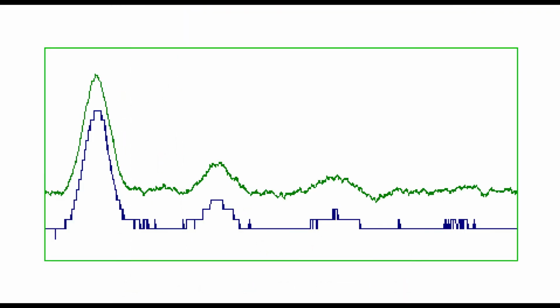The following figure shows the same chromatogram as before with a small amount of noise added. The noise appears as quantum hairiness on both the baseline and the peaks. When the noise spans several steps, the hairiness fades, and the quantized noise appears as shown in the first figure in this section. Note that the fourth peak, which had vanished into the baseline in the overlay plot above, has returned as a region of dense hairiness. When the noise in the signal is about equal to the step size, it has the paradoxical effect of increasing the resolution.